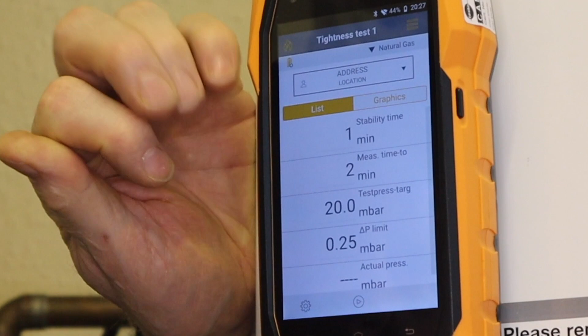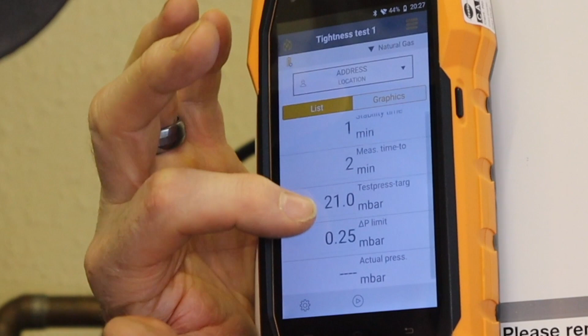And what we've got here is a stability time of 1 minute. It says a measurement time of 2 minutes, and it says tightness pressure target 20 millibars. Well, actually a tightness test is between 20 and 21 millibars, so if I click on that, again, I can change it to 21, press the tick, and it's now changed to 21. And we've got a minimum of 0.25, which we don't need to change, and then it's got our actual pressure there.